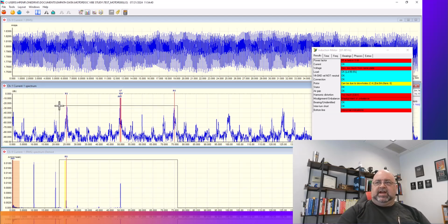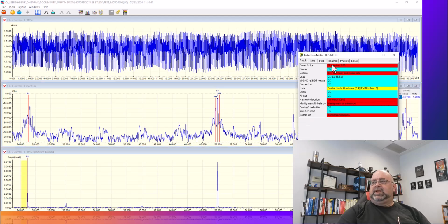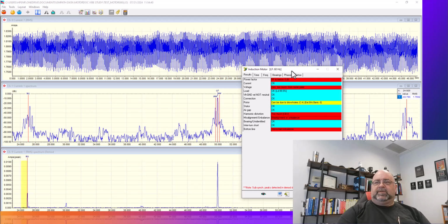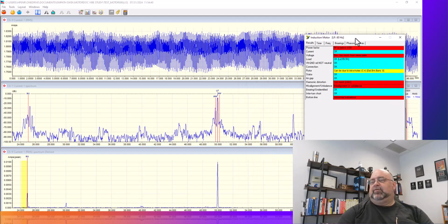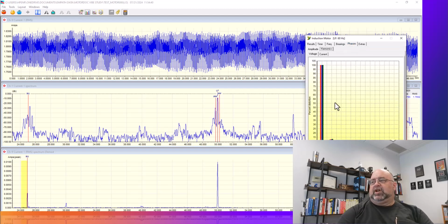You can see that I'm able to zoom in relatively easy. And all of those extra peaks all mean something, by the way. So there we go. Showing the multiple peaks here, a lot of sidebands around it. That's a combination of noise, and that did have corona. It did have electrical discharge because I saw both corona and PD with the camera on this machine. And then I can also look at harmonics in both current and voltage.